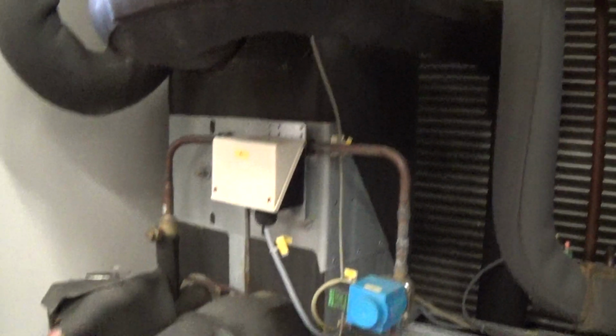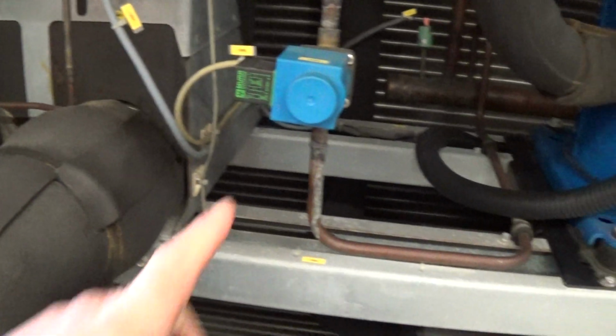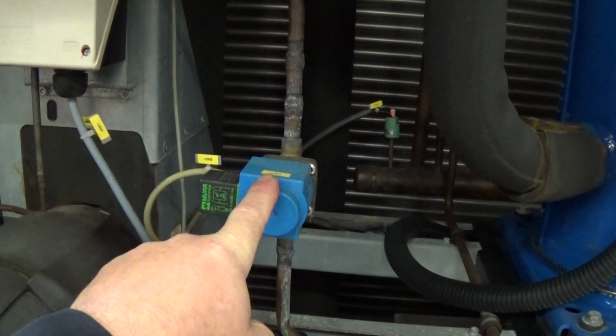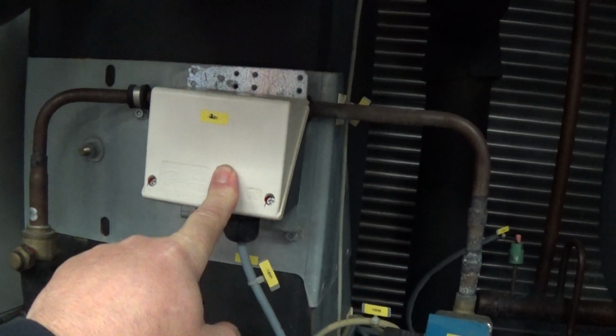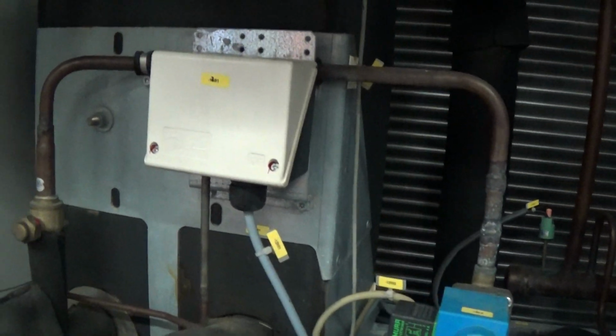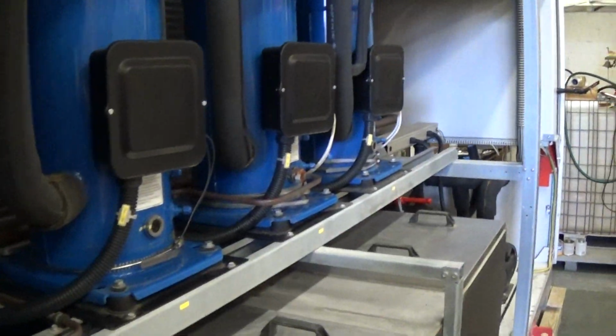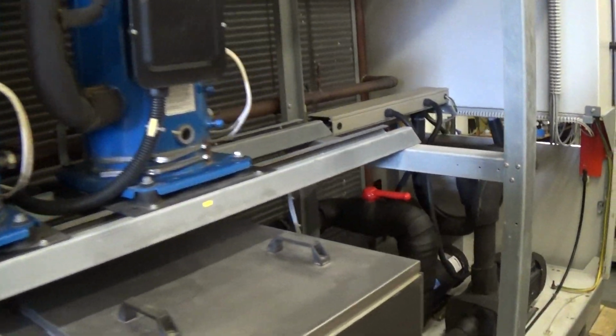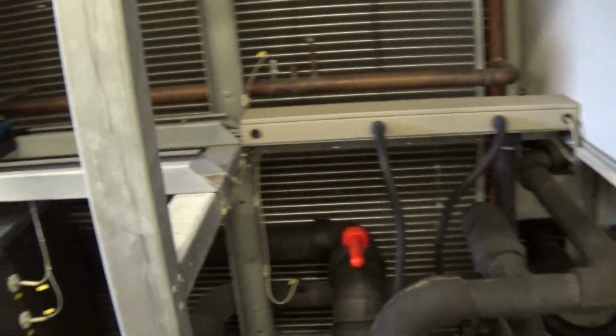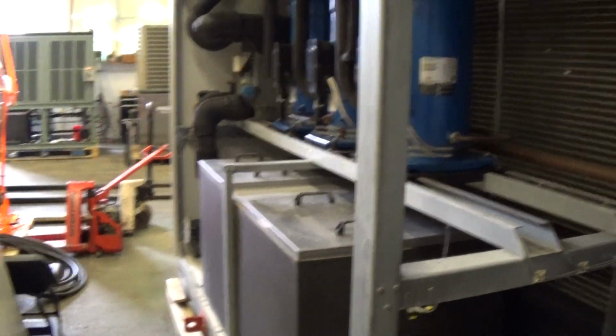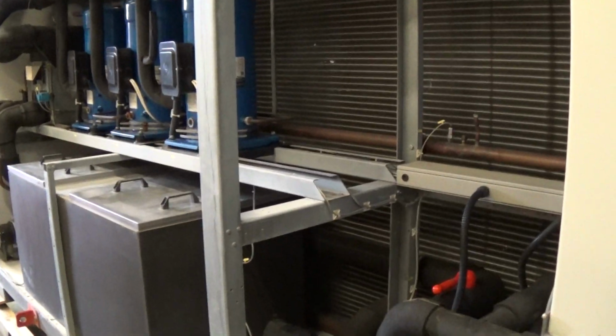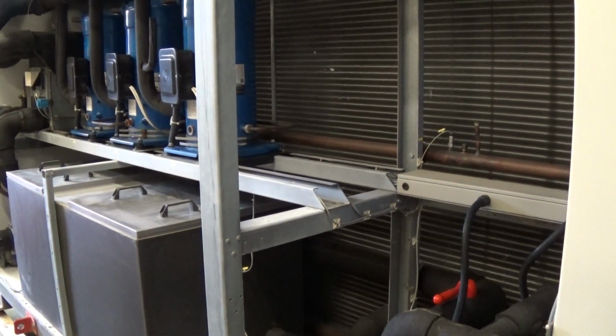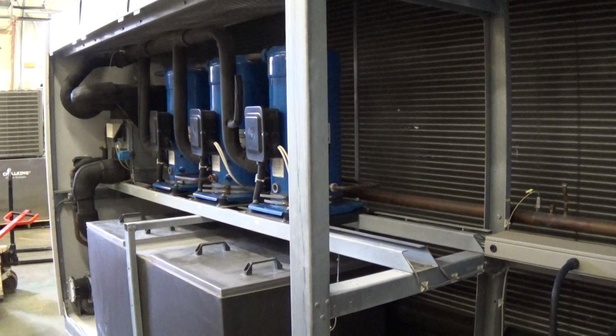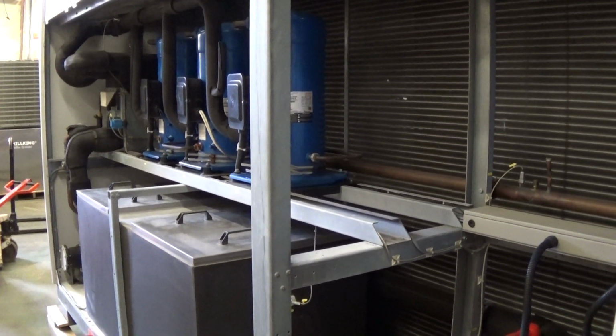So again, this is our brazed plate evaporator, 3 compressors, 1 refrigerant circuit. On this unit here, we do have a hot gas bypass solenoid valve, and the hot gas bypass can be adjustable by going behind this box and making an adjustment. A hot gas bypass sometimes can be your friend and sometimes not for different applications. Some chillers don't even have it. Hot gas bypass is a method of capacity control if you are running at lower tonnage or reduced capacity situations. The hot gas will actually bypass gas in the circuit, and it will prevent short cycling of your compressors from starting on and off.